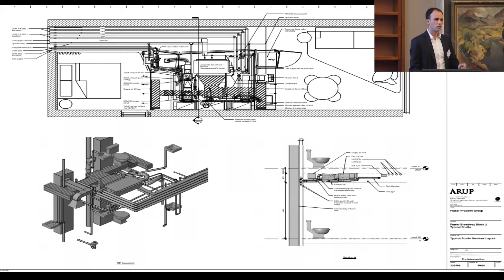The central thermal plant approach dictates certain things in terms of metering. It's heavily metered throughout the site to allow billing to take place. A traditional square metre pro rata billing approach wasn't really good enough, and it wasn't seen to be equitable, so all of the fan coil units had electrical meters to determine, as a proxy, the amount of consumption of each unit, which was used for billing.